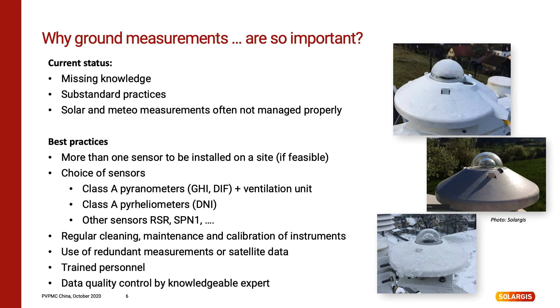But we see a lot of struggling with measurement campaigns. Usually there are missing skills and knowledge about maintenance procedures or low standard practices. Very often we see sites with many meteorological stations delivering tons of measurements, but nobody cleans the sensors regularly. Or even worse, data from these sensors are combined into one dataset as gap filling in case of failure of some sensor. So the result of such practices is that measurements are not managed properly, which degrades the quality of the whole measurement campaign. To avoid or minimize risk of wasting resources, it is good to plan campaigns with only several pieces of high-quality sensors. Depending on the site, two or three secondary standard pyranometers may be enough to have redundant data in case of sensor failure or to have a reference for comparison between them.